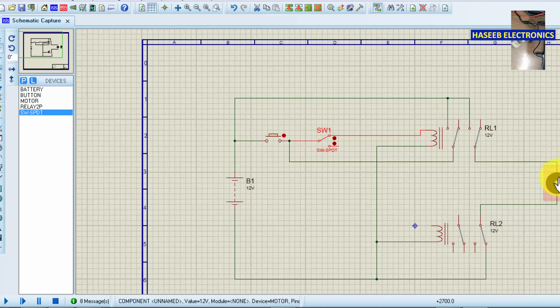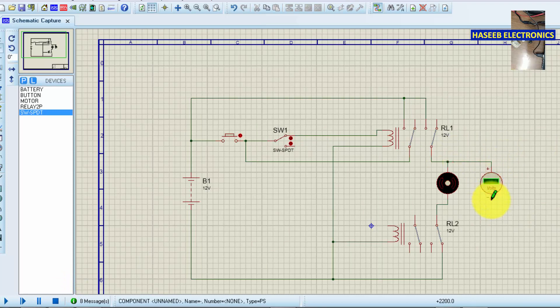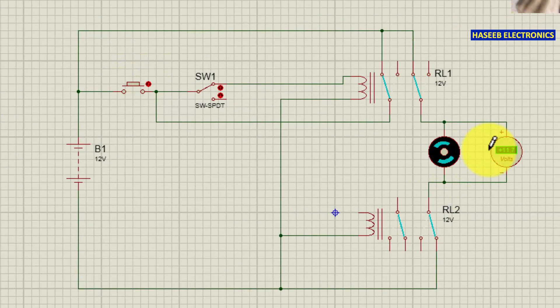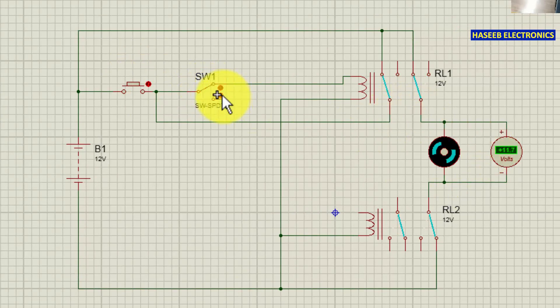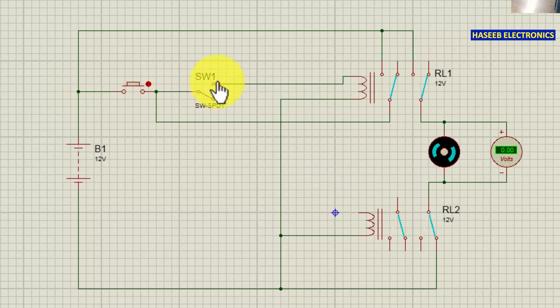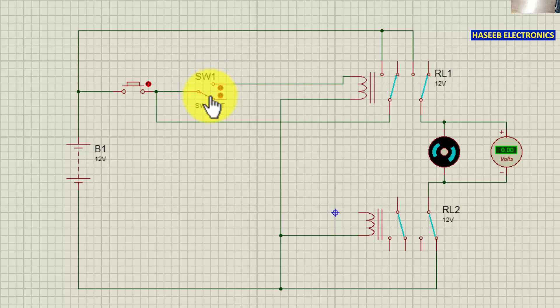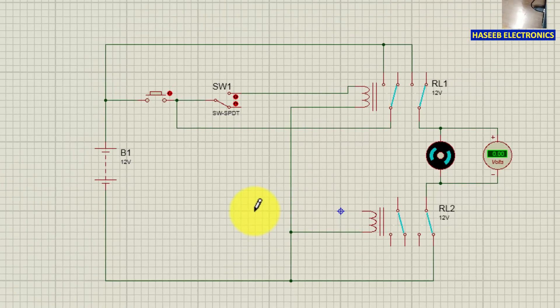Let's connect the multimeter and power on. I will push the switch and the motor runs. When it reaches the upper limit it will shift the micro switch and the motor will turn off. When we pressed the button, supply passed through the push button and micro switch, energizing the relay. After that, the positive voltage latched through the relay itself. When the barrier reached the upper limit, the micro switch shifted and disconnected the circuit.